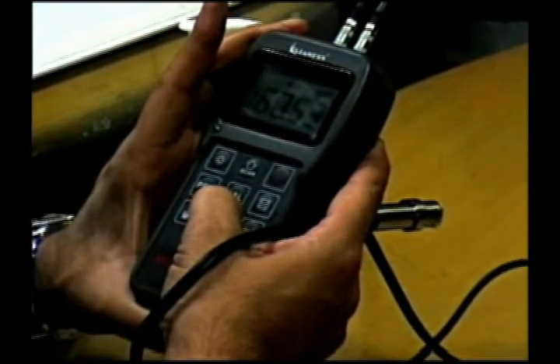And then we simply bring the value of the known thickness to the point which we had measured, which in this case was 12.98 mm. Once the 12.98 mm reading is over here and the mm button is still flashing, then we press the cal button once again.